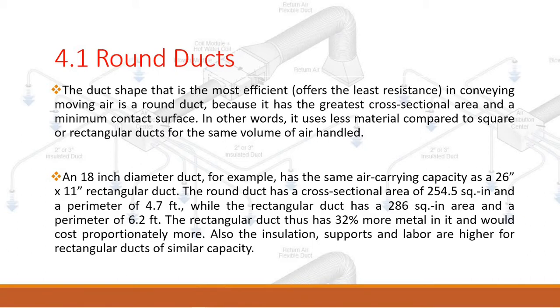The round duct has a cross-sectional area of 254.5 square inches and a perimeter of 4.7 feet, while the rectangular duct has a 286 square inch area and a perimeter of 6.2 feet. The rectangular duct thus has 32 percent more metal in it and would cost proportionately more. Also, insulation, supports, and labor are higher for rectangular ducts of similar capacity.